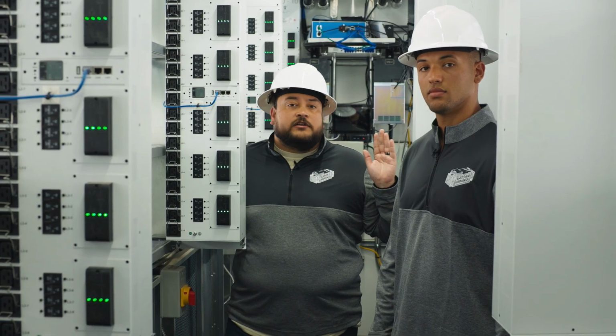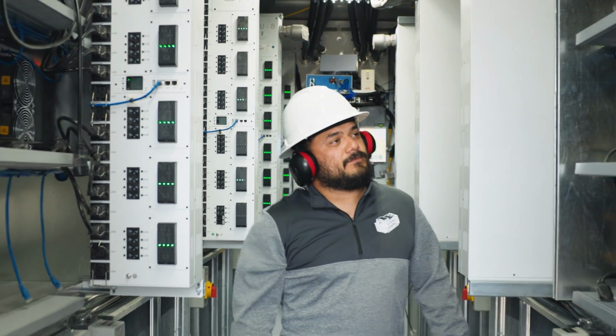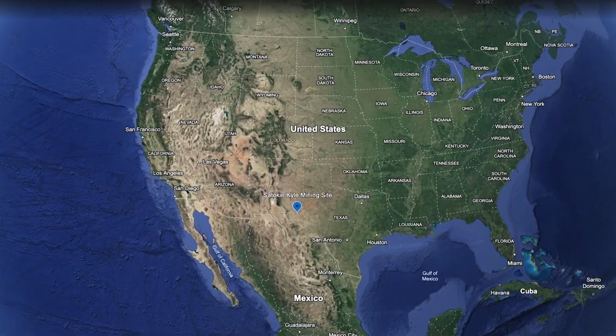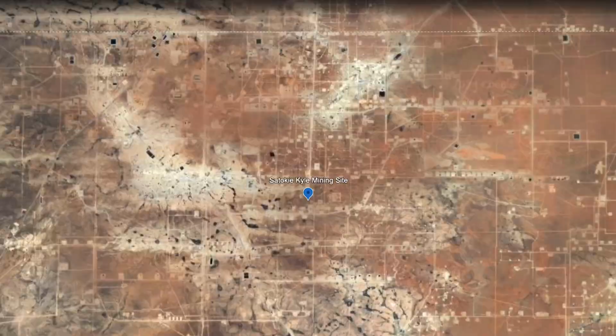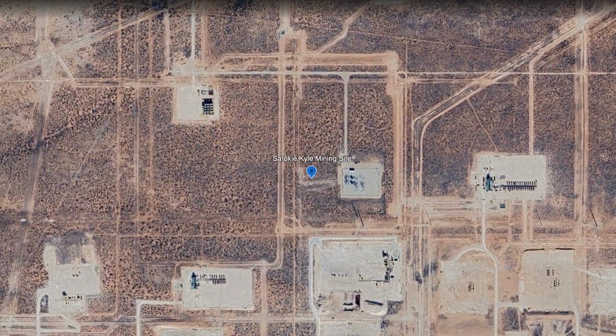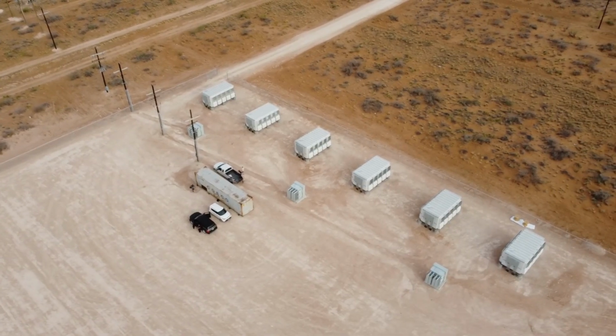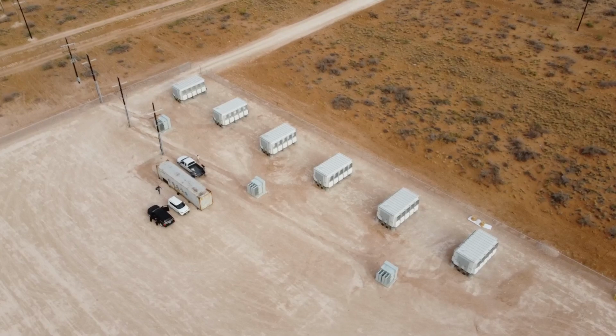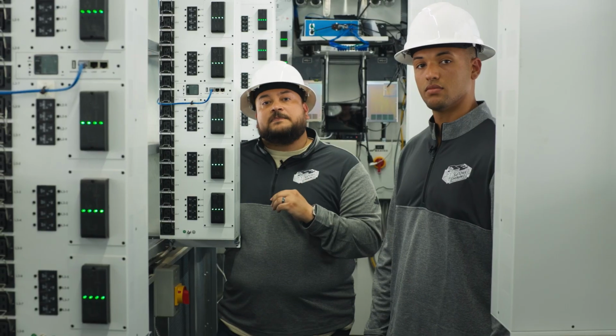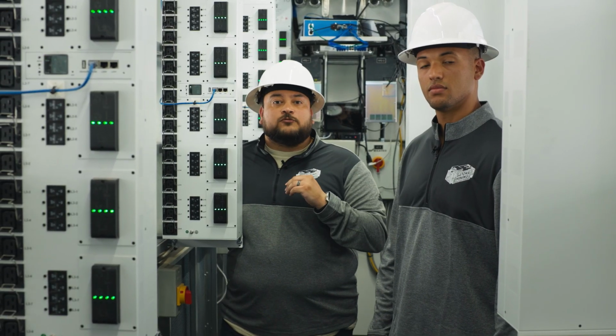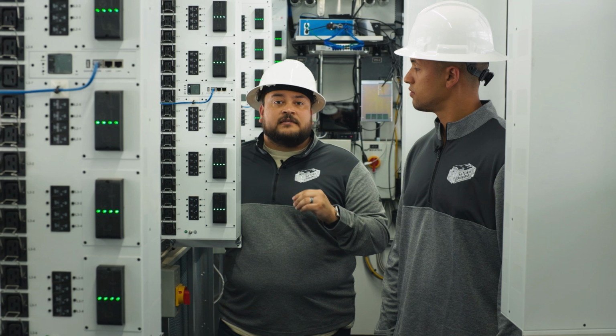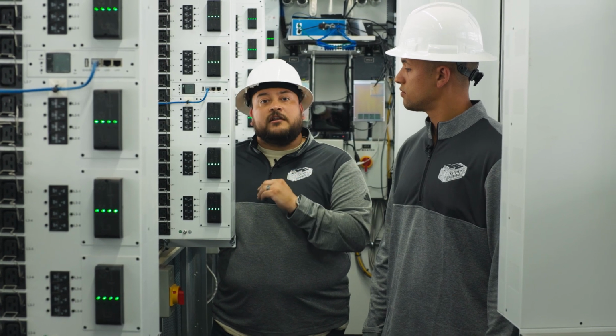Also, airflow is critical when doing air cooling in an environment. We're currently in West Texas, and it's very challenging to run here because of the weather. It's really, really hot here. And so we need to make sure that we have the highest amount of airflow possible. And this specific spec of container has one of the highest CFM ratings specifically to be able to run air-cooled units.